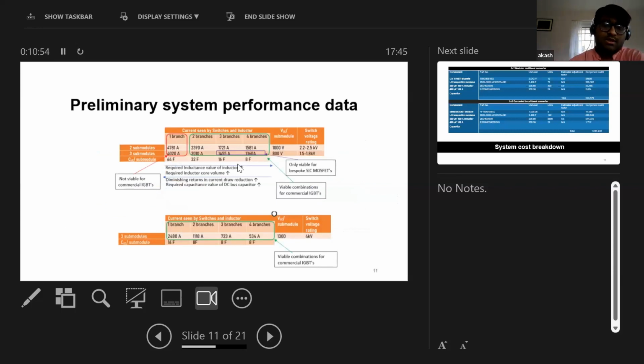So this summarizes the analytical data over different topologies of the two designs I presented. If you have a cascaded boost converter with two or three submodules within a branch, and also over four branches, these are the max values of current discharge you will see with these expected switch voltage ratings. Obviously, the rating of the submodule voltage is derated to about 40 to 50% of the actual switch voltage rating for safety reasons.